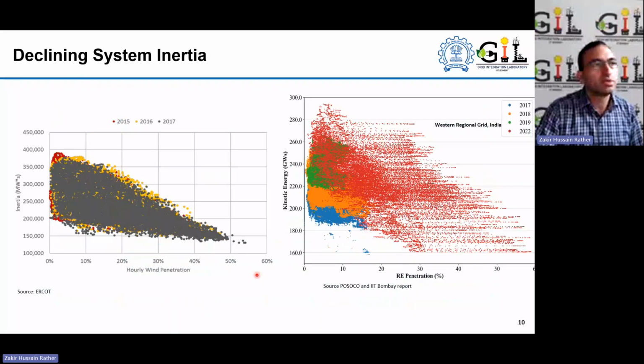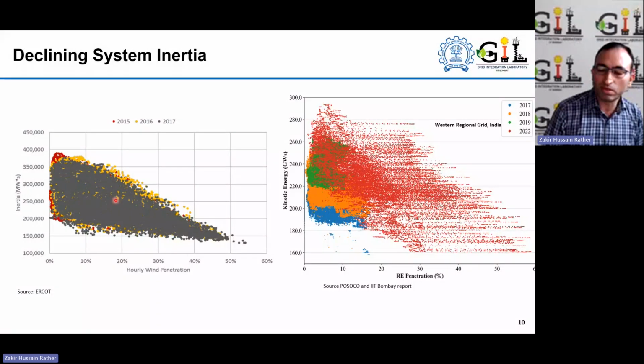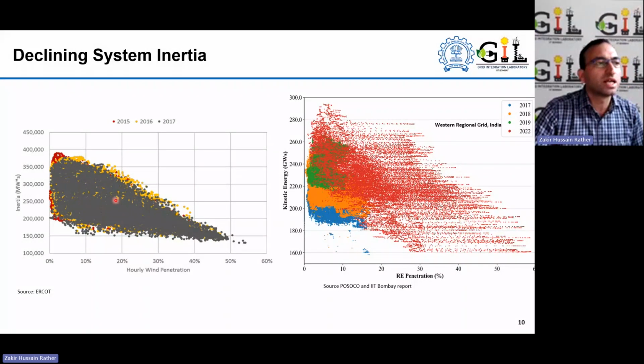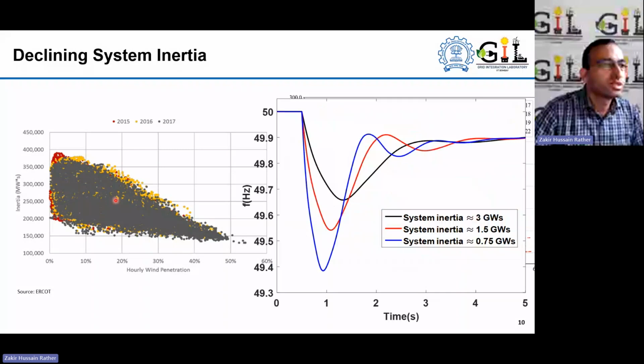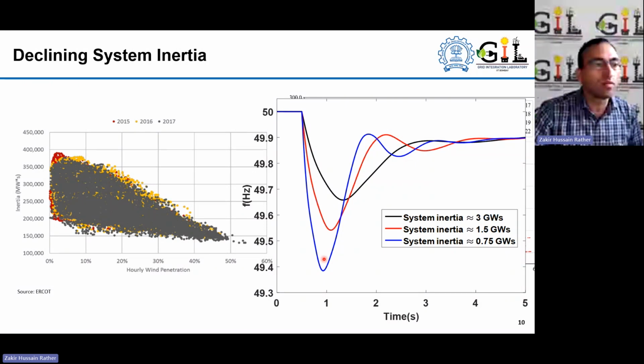These are some examples of the impacts of IBR integration. Inertia is one of the important parameters of the grid that declines, for a very obvious reason, with the increase in IBRs, because we are displacing the rotating mass in the grid. As a result, there are frequency stability concerns, particularly with the maximum rate of change of frequency in the system following any sudden generation-load imbalance. This is a simple test study that we have done here at IIT Bombay to show how, for the same system and same contingency, with increased penetration of renewables, the frequency nadir and the rate of change of frequency deteriorate further and further with an increased share of renewables in the system.